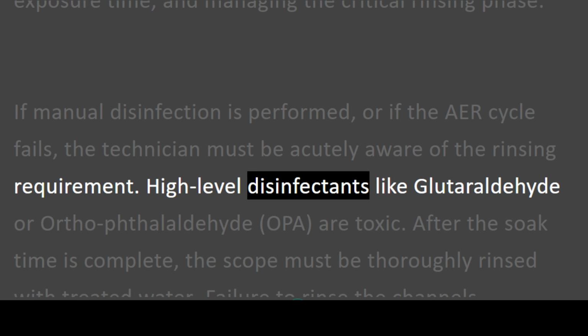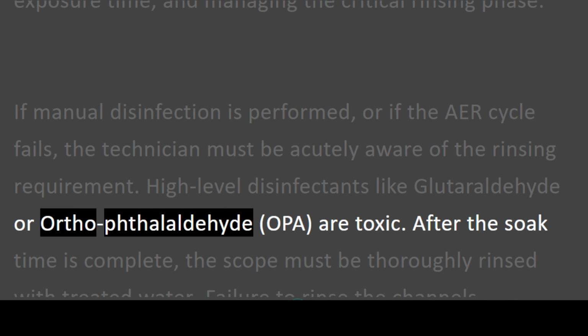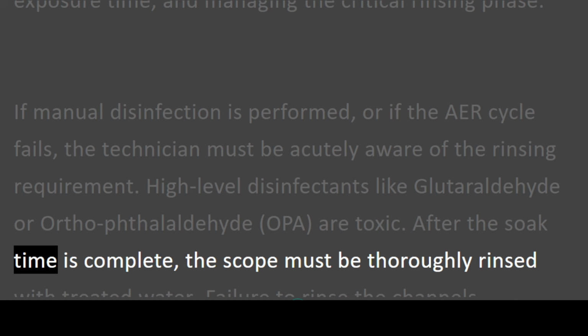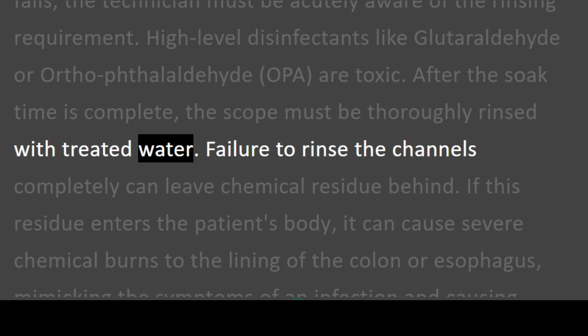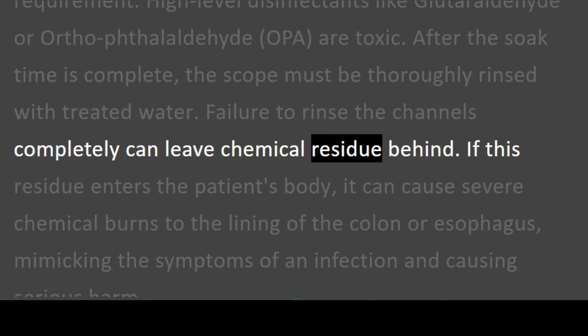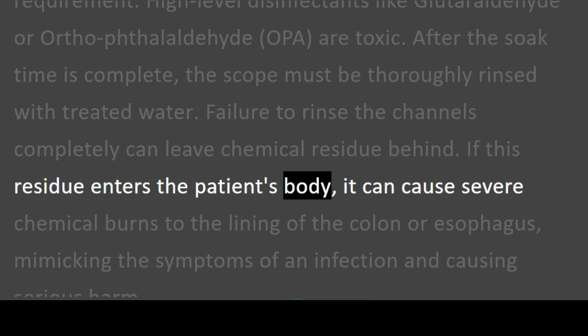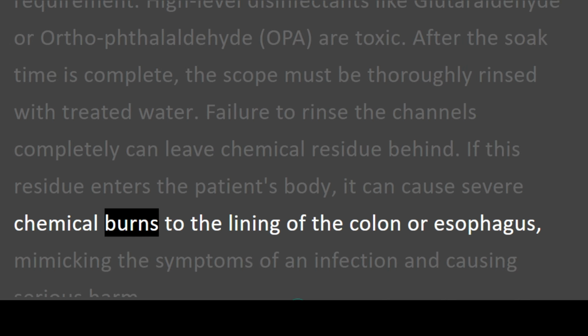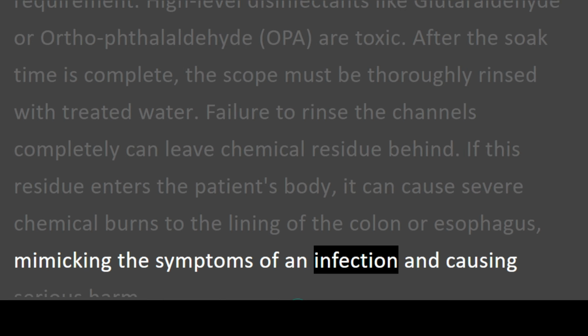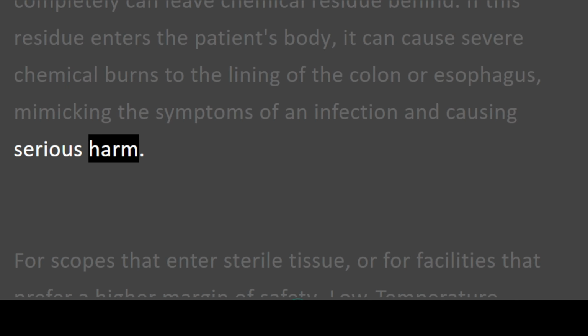High-level disinfectants like glutaraldehyde or orthophthalaldehyde, OPA, are toxic. After the soak time is complete, the scope must be thoroughly rinsed with treated water. Failure to rinse the channels completely can leave chemical residue behind. If this residue enters the patient's body, it can cause severe chemical burns to the lining of the colon or esophagus, mimicking the symptoms of an infection and causing serious harm.